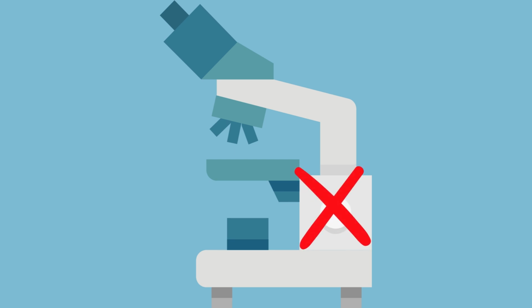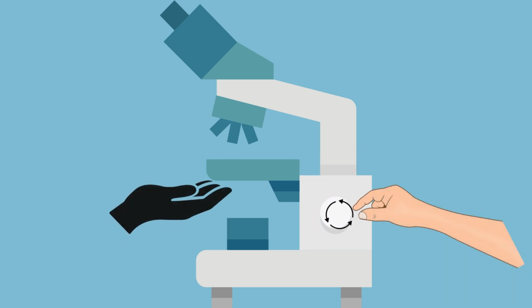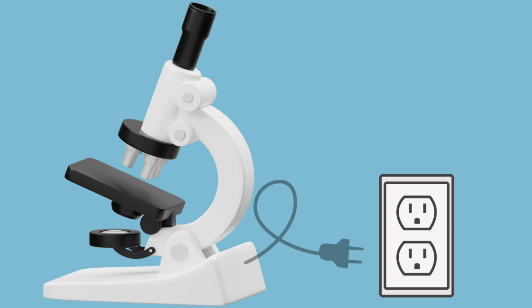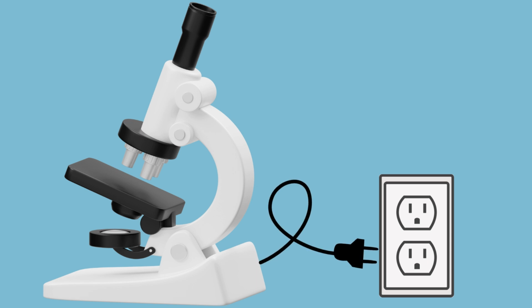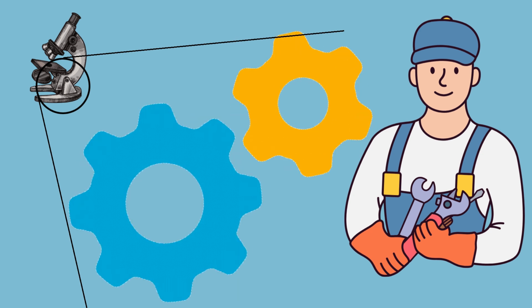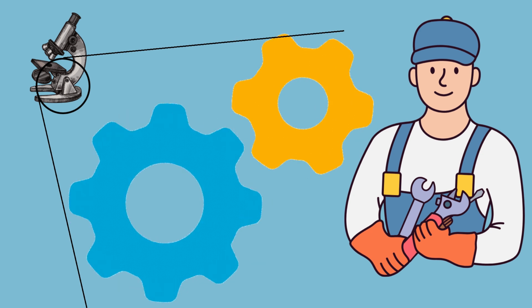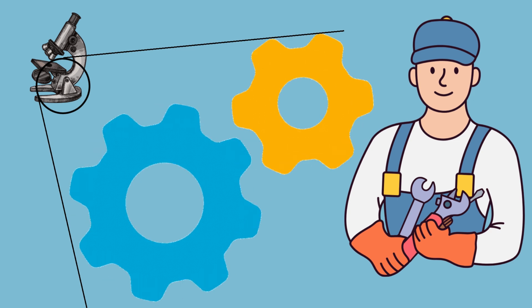Should you encounter mechanical issues, like difficulty in adjusting the focus, verify that the focus knobs are not too tight or too loose and that the stage moves smoothly. Electrical problems often come down to power connections. Ensure your microscope's plug and cables are intact and the power source is reliable. A loose focus can be corrected by tightening the focus locking ring. If that doesn't help, the internal gears may need professional attention.